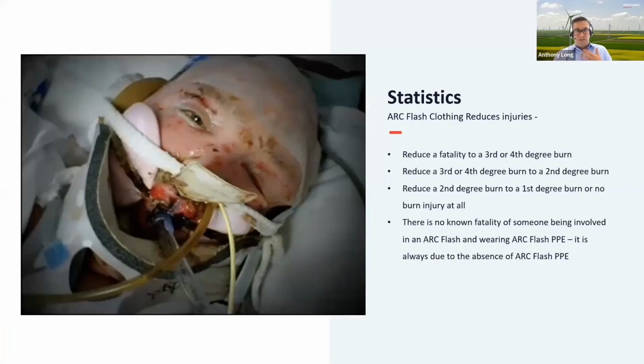So looking at some statistics here, arc flash clothing is designed to reduce the fatality to a 3rd or 4th degree burn. Turning the clock back a few years, you very rarely heard of 4th degree burns, because generally speaking a 4th degree burn was a fatality. 3rd degree burns you heard of, but a lot more these days, burns units do a phenomenal job, and so we still do see survivors from 4th degree burns. But basically, 3rd or 4th degree burn, you're reducing those to a 2nd degree burn, and 2nd degree burn to a 1st degree burn, or no burn injury at all.